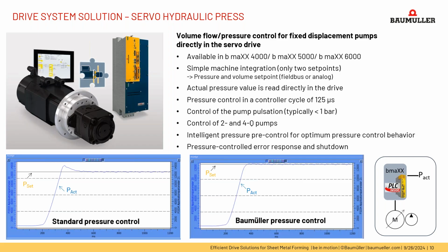The servo pump software interacts directly with the drive CPU at 125 microsecond cycle time. This results in very precise pressure control that reduces pressure overshoots and can control the pump pulsations to values typically less than 1 bar. Our system can operate 2 or 4 quadrant pumps. It is therefore also possible to reverse the direction of the flow.